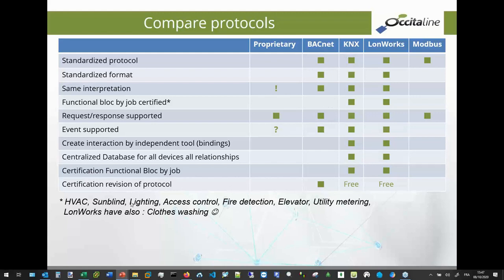Functional blocks certified by job are more critical. In KNX and in LON, the two groups, LonWorks International and the KNX organization, have created these functional blocks. These functional blocks describe some activity, some job: HVAC, sunblind, lighting, access control, fire detection, and so on. In BACnet, it's very poor. We have some objects, but an object is not exactly the same as a functional block. A functional block for a light or a sunblind has several data points. An object in BACnet has just one data point inside.